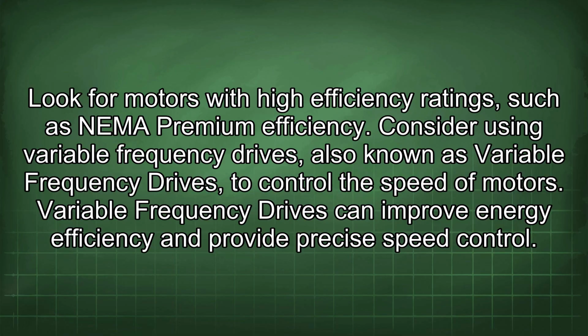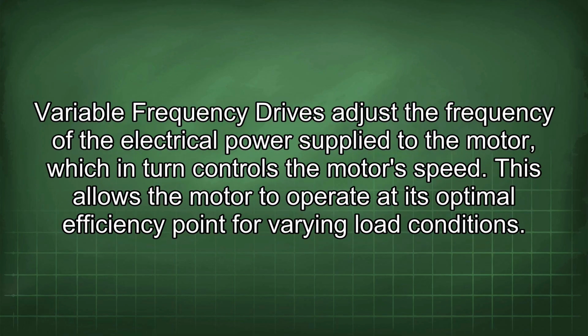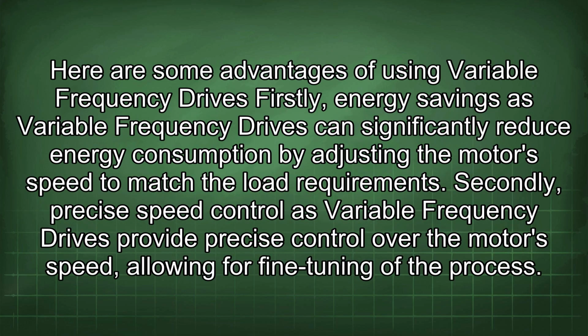Consider using variable frequency drives to control the speed of motors. Variable frequency drives can improve energy efficiency and provide precise speed control. Variable frequency drives adjust the frequency of the electrical power supplied to the motor, which in turn controls the motor's speed. This allows the motor to operate at its optimal efficiency point for varying load conditions. Here are some advantages of using variable frequency drives. Firstly, energy savings, as variable frequency drives can significantly reduce energy consumption by adjusting the motor's speed to match the load requirements.